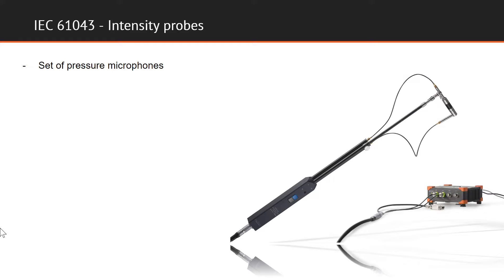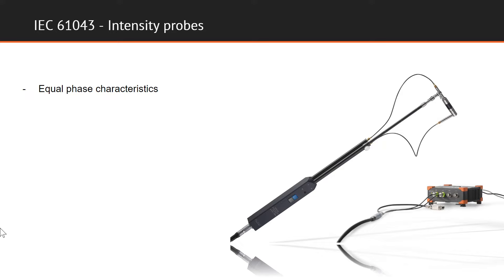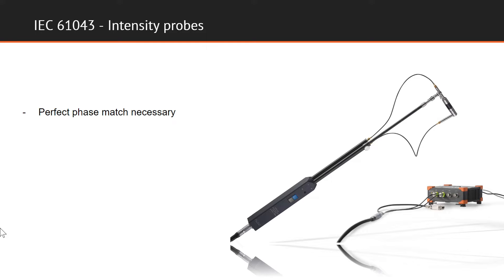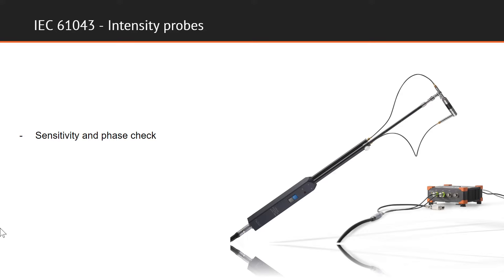Sound intensity is generally measured with sets of pressure sensing microphones that are attached to sound intensity probe. A set consists of two microphones with phase characteristics which are essentially equal. A very close match is necessary, as even small phase response differences may cause significant errors of the measured intensity. Sound intensity probe calibration procedure consists of sensitivity and phase check. The sensitivity of the microphone pair is measured by comparison with the reference microphone, according to the same procedure as described in IEC 61094 for calibration of measurement microphones.